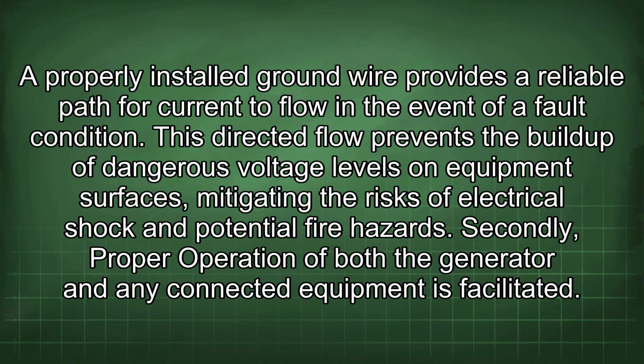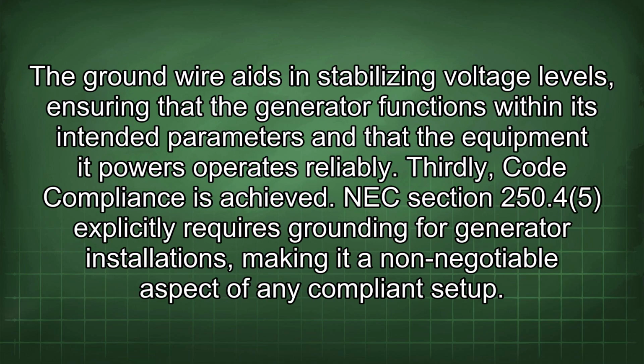potential fire hazards. Secondly, proper operation of both the generator and any connected equipment is facilitated. The ground wire aids in stabilizing voltage levels, ensuring that the generator functions within its intended parameters and that the equipment it powers operates reliably. Thirdly, code compliance is achieved. NEC Section 250.45 explicitly requires grounding for generator installations, making it a non-negotiable aspect of any compliant setup.